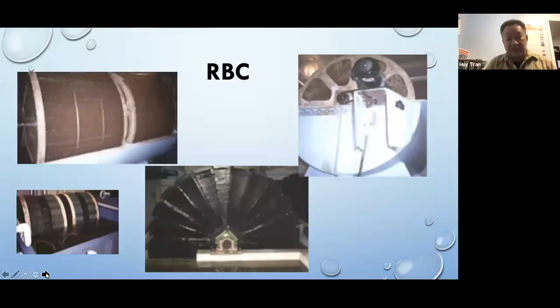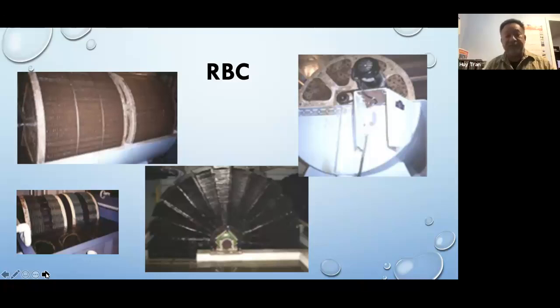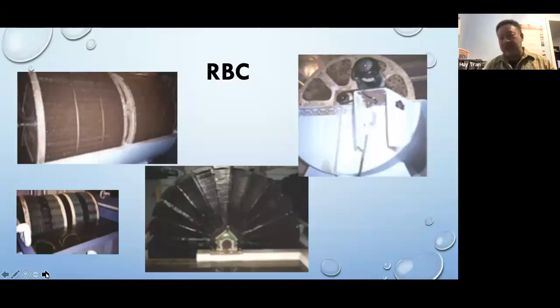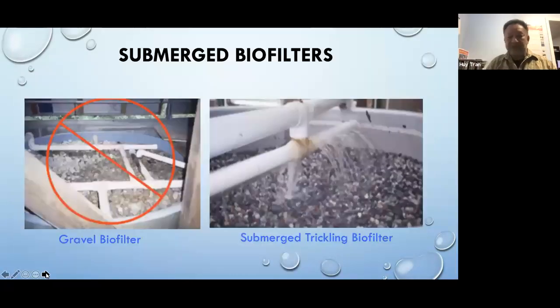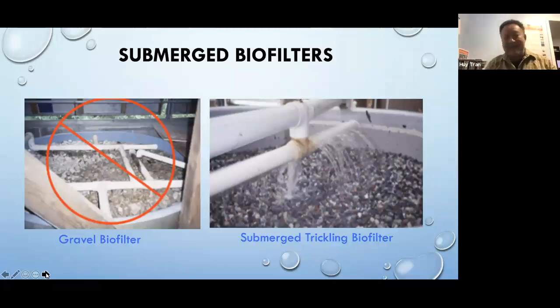Rotating biological contactors (RBCs) can get very heavy — I've seen a three-inch steel shaft bent from the weight after long-term bacterial population. Some floating RBC designs use air rotation, but over time bacteria can populate unevenly, making them lopsided and reducing rotation. RBCs are harder to clean, weight becomes an issue, and water distribution through them is a challenge.